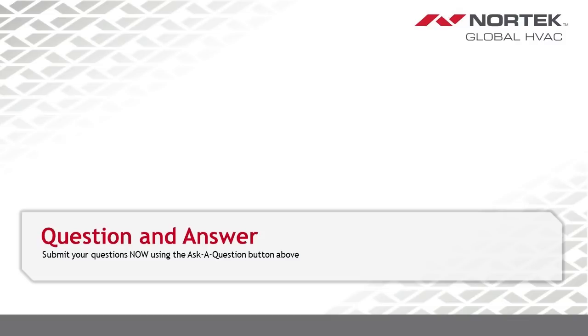Another general question: do we expect any problems with zoning on the new furnaces? No, it would be similar to what you'd expect today, where the CFM delivered at the outlet of the furnace is the same — it's just how the airflow is delivered. The only time you'd run into a problem would be with variable speed, because the variable speed blower will fight the zoning in the ductwork. But most product we sell today is fixed speed ECM, and those will have no problem delivering airflow in a zoning system just like product does today.